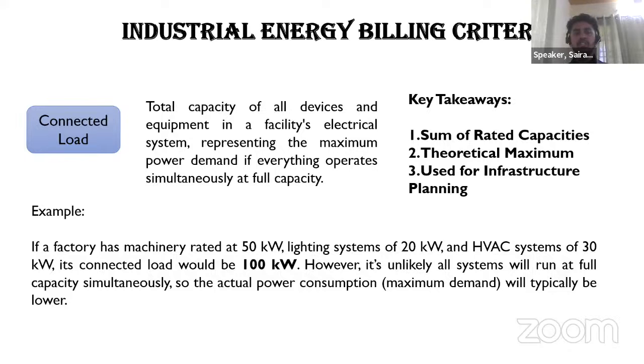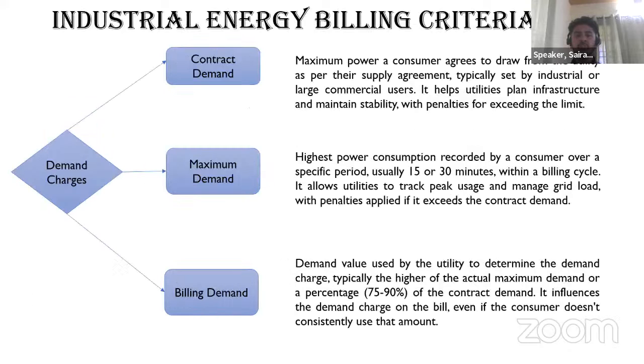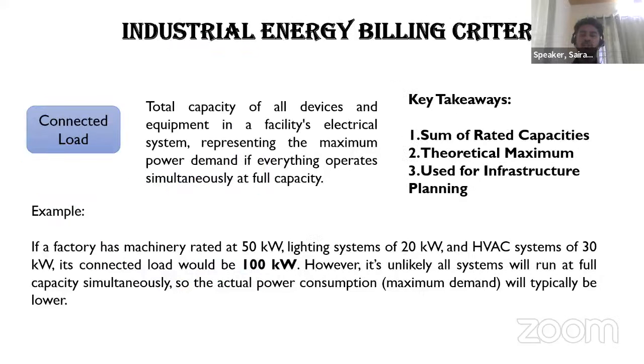Then coming to the connected load. This connected load is the major factor for determining the contract demand. If you know what utilities are there at your industry that are connected to the electrical grid, and you will be using them for production or any other activities, then you can plan for the contract demand. The connected load is the sum of the rated capacities of all the equipment present at the industry. It also explains the theoretical maximum: if all the equipment at the industry operates at the same time, what is the maximum demand that can be reached by the connected load.